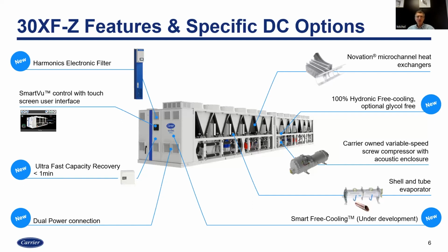I don't have specific slides about the compressor, but this is the latest generation—100% free cooling, 100% variable speed drive compressor. We don't have slide valves anymore in this compressor; it's designed with the latest technology, very high efficiency, using only variable speed drive to adjust to the capacity required. It also has an integrated automatic VI adjustment—in the compression world, that's the ratio between discharge and suction volume. I won't go into detail, but this option makes the compressor's adaptability to conditions and load very unique.